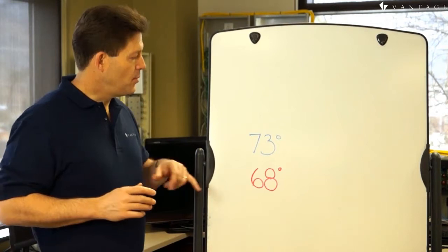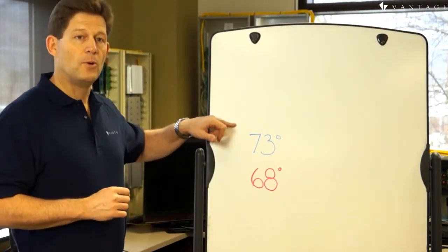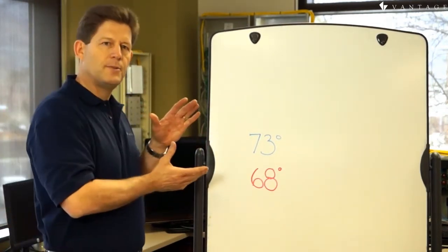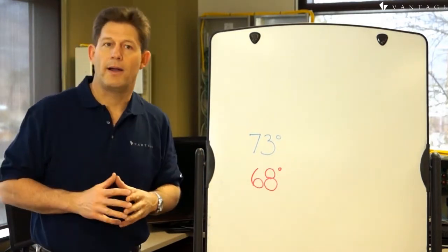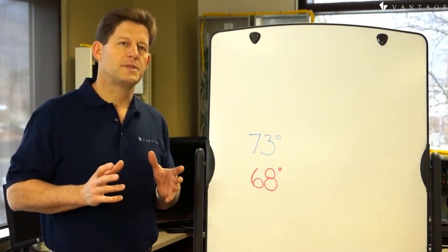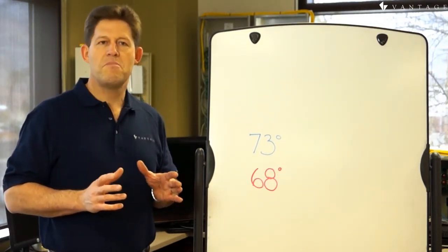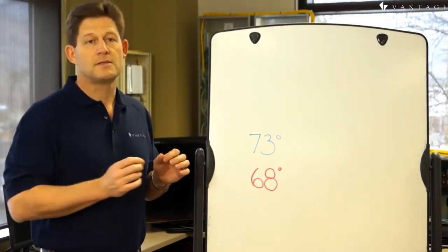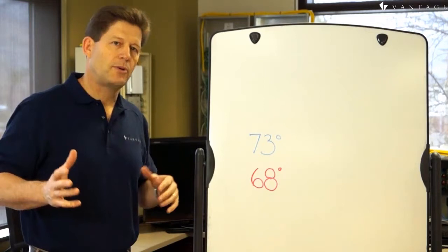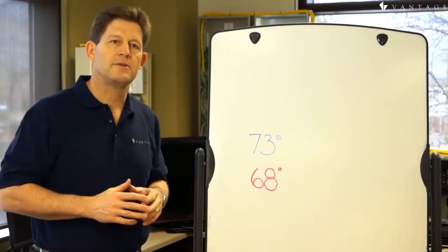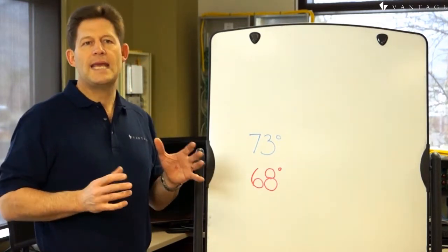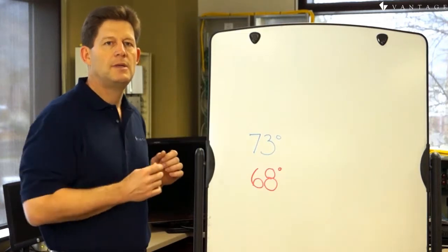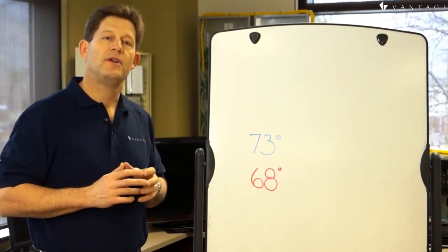A heat set point will always be lower than a cool set point; otherwise there would be a temperature range in which heating and cooling are both required. In fact, many thermostats enforce a minimum separation between these set points, sometimes fixed and sometimes variable, typically two to three degrees difference, that keeps us from setting the heat and cool set points too close.